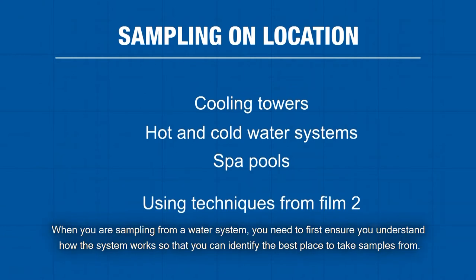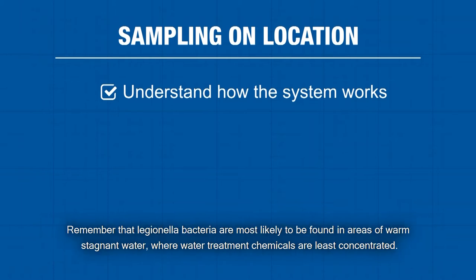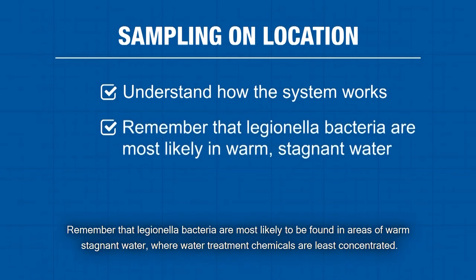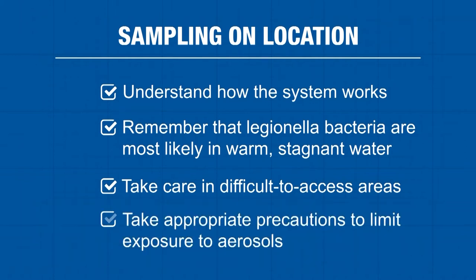When you are sampling from a water system, you need to first ensure that you understand how the system works, so that you can identify the best place to take samples from. Remember that Legionella bacteria are most likely to be found in areas of warm, stagnant water where water treatment chemicals are least concentrated. You need to take care when sampling, as some equipment can be in locations that are awkward to access, and you should always take appropriate precautions to limit your exposure to aerosols from potentially contaminated water.